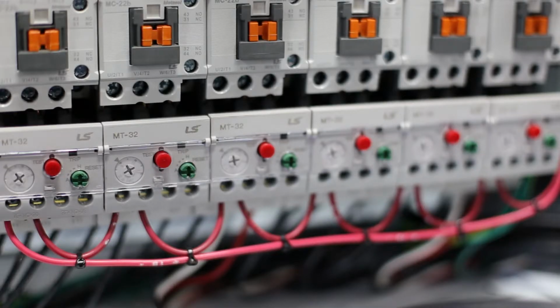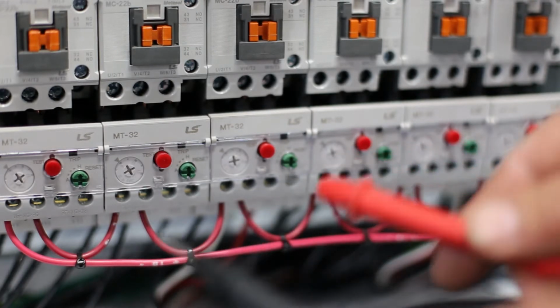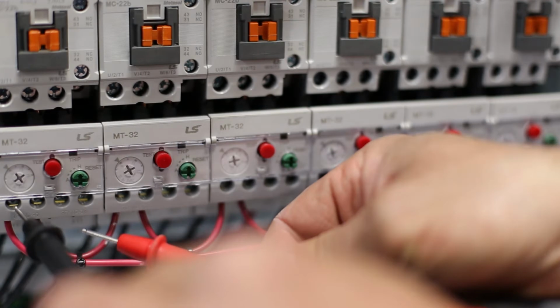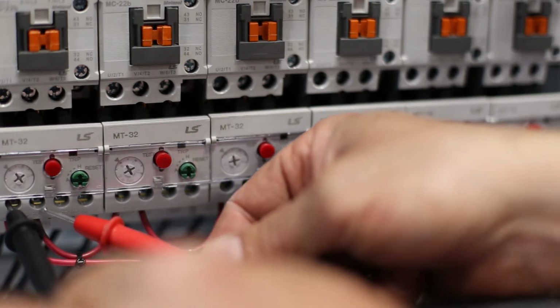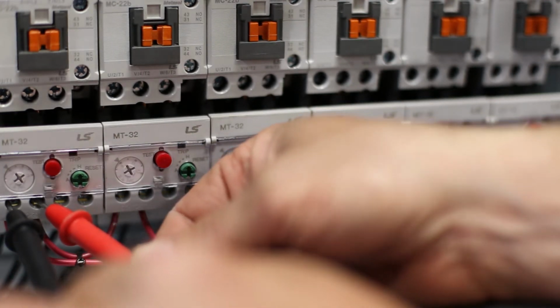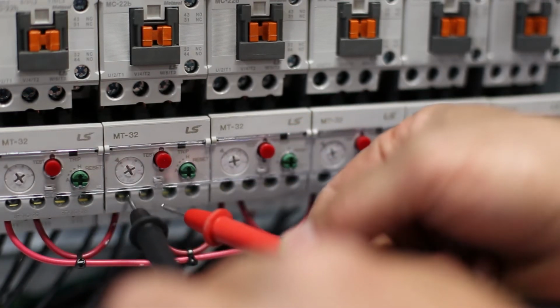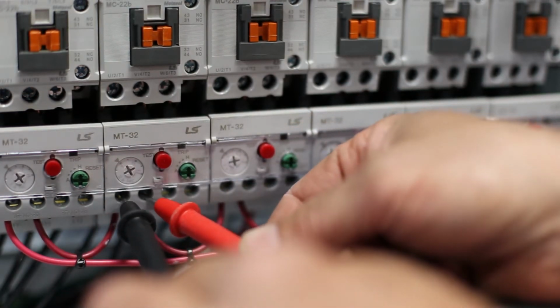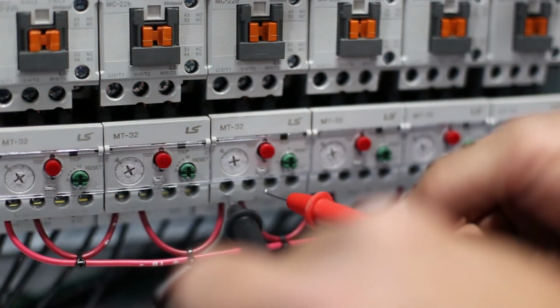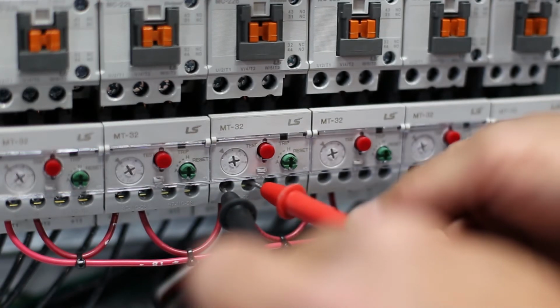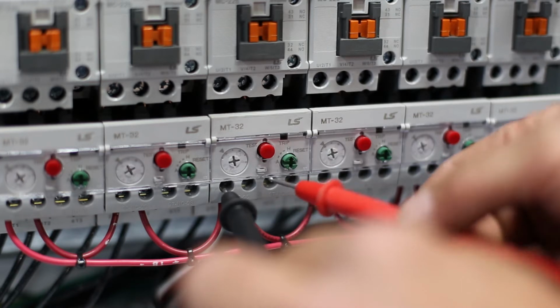Okay, now that we located the overloads in our high freq panel, make sure our power is off again, locked out, tagged out. We're going to check the ohms between each overload to make sure that they're closed. So if you go down here at the bottom, you go between the first screw on the left and then the second screw, you want to check each one to make sure they ohm out. If one of them doesn't ohm out, that means we have a tripped overload. So for example, on this one here, this one didn't ohm out.